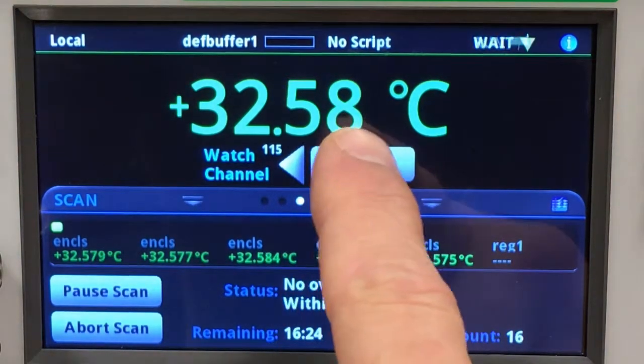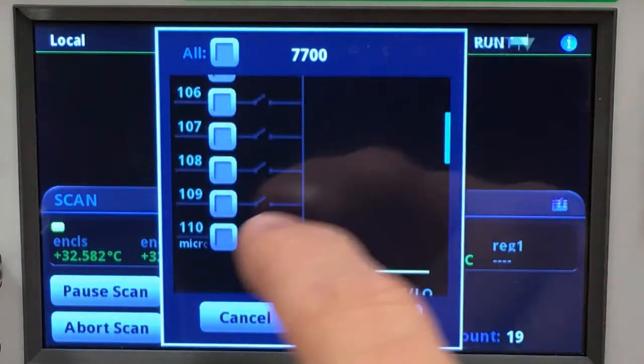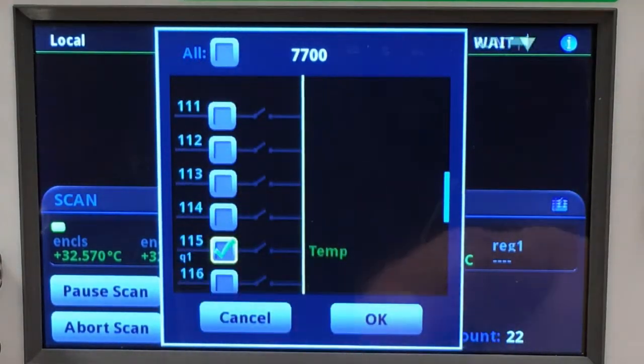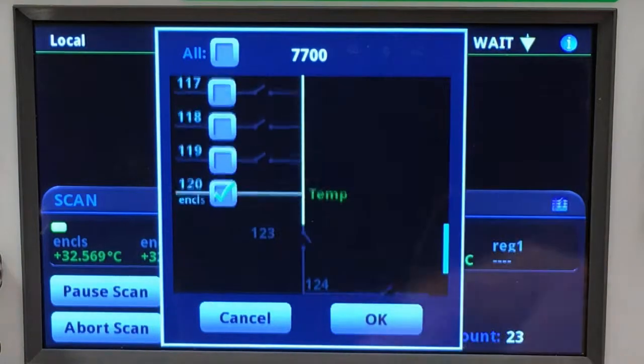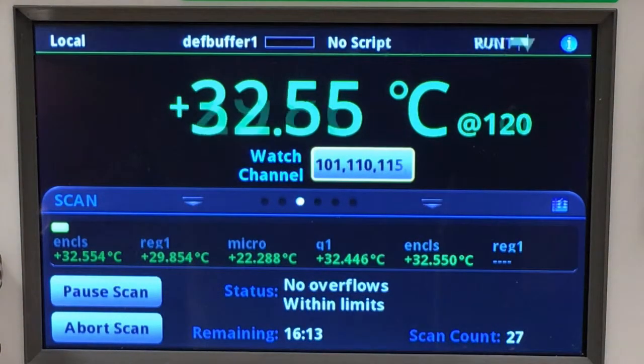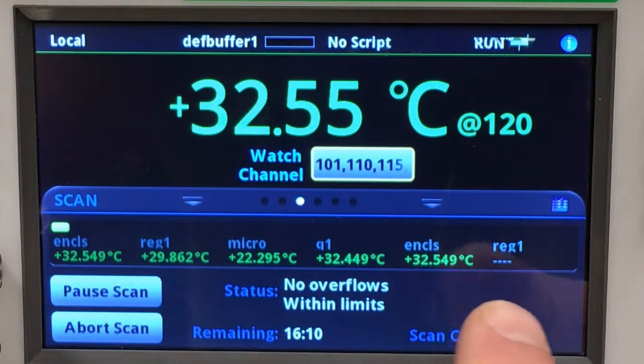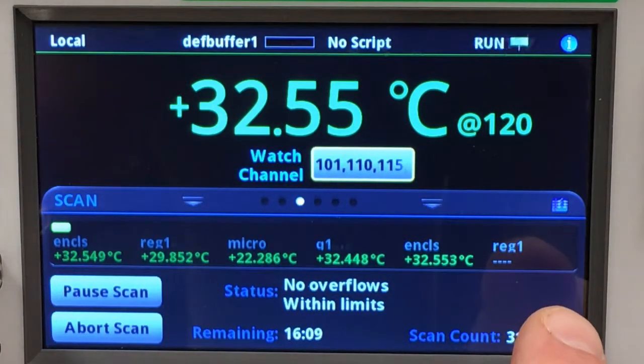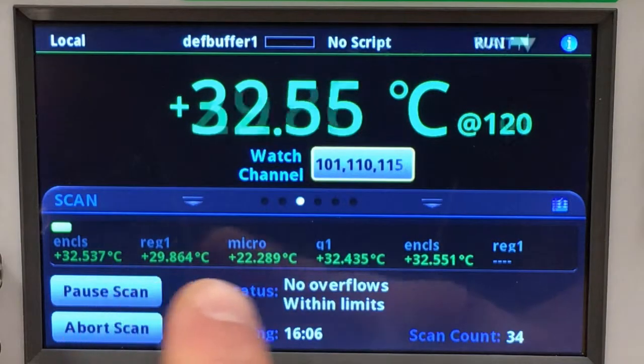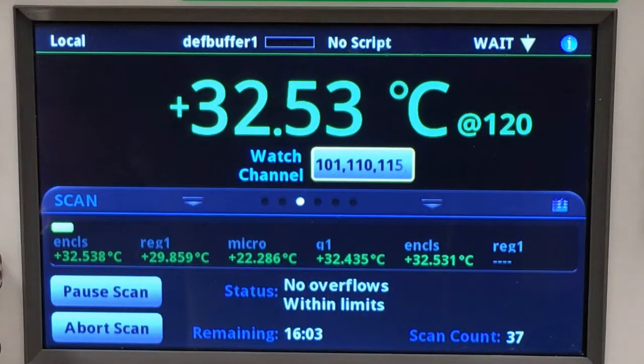Let's go ahead and look at each individual channel. Channel 120 is still selected by default — I accept. Now you can see that the carousel is monitoring each of the four channels and letting us know by the label we applied what measurement goes with what channel.